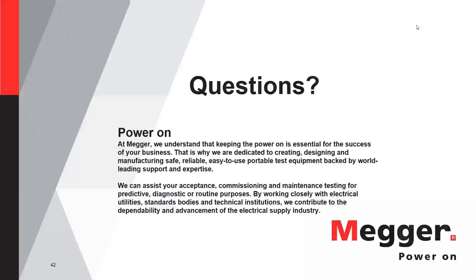I think on transmission cable, that's what people sometimes do. They are really only concerned about splices and terminations, so they have permanent detectors in those devices, and they are permanently monitored, so that can be done. But on a distribution cable, I think it would be very difficult to get an economic system in place that could do a rather long distribution cable with an online PD test.